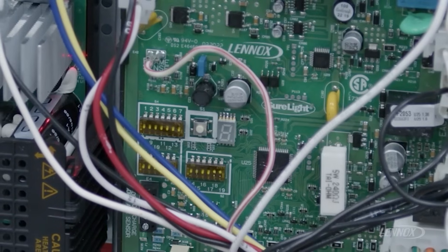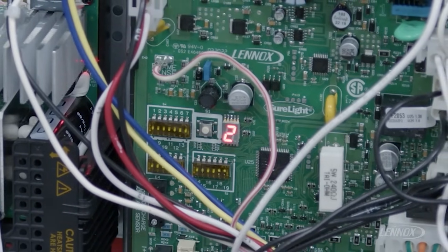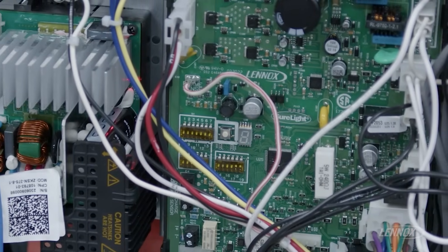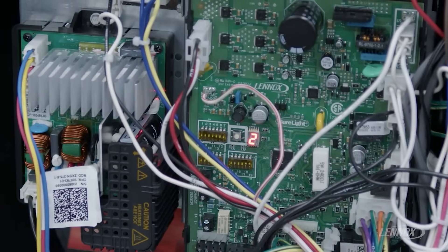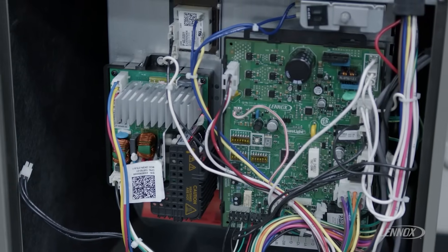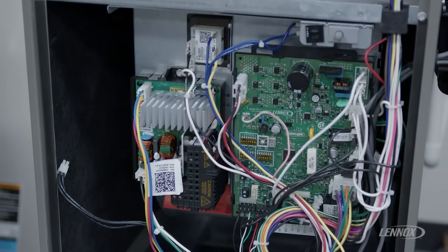How this reads is that we have lost communication with the indoor blower motor. Some possible causes here include things like power outages, brownouts, motor not being powered, loose wiring, condensation on components, or potentially an issue on the motor side.